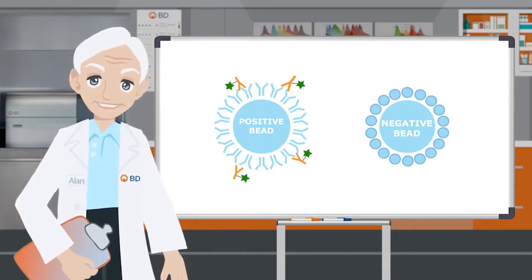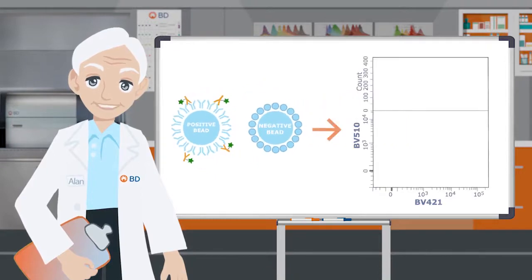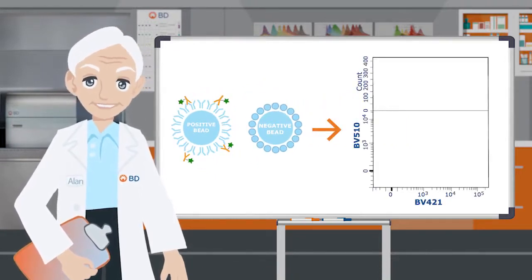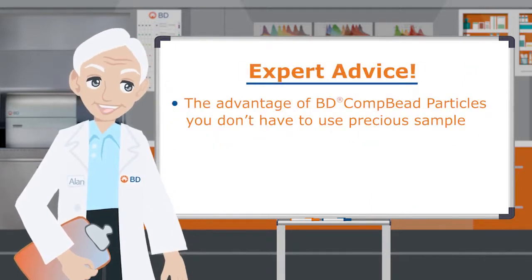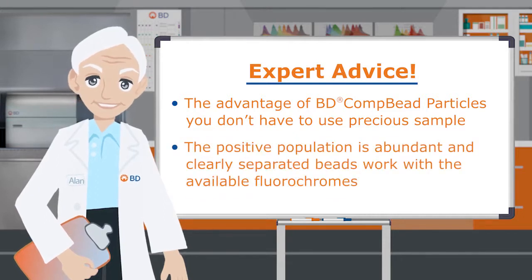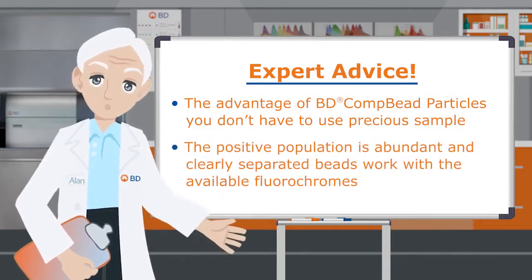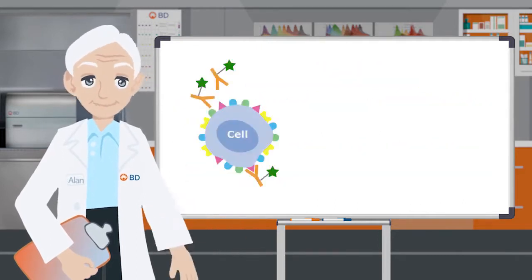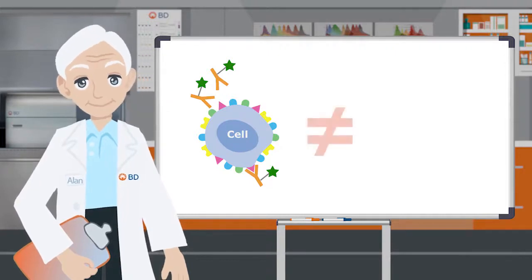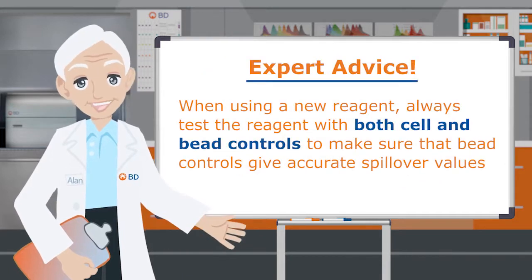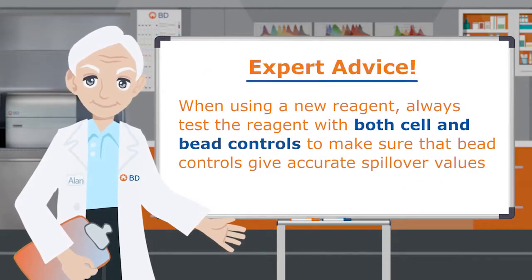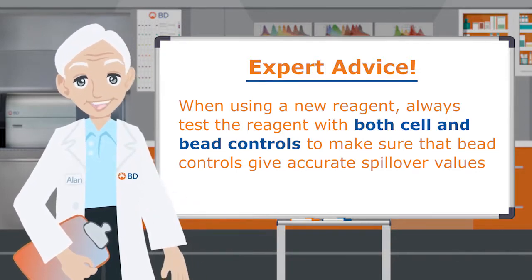When using cells is not practical, antibody capture beads can be used as a valid alternative for most fluorochromes. BDComp bead compensation particles, for example, are coated with anti-immunoglobulin that bind most fluorescent conjugated antibodies, acting as a surrogate for stained cells. The advantage of BDComp beads is that you don't have to use precious samples, and the positive population is abundant and clearly separated. The beads work with most of the available fluorochromes. However, it is important to note that for some fluorochromes, the spillover values on beads can be significantly different from similarly stained cells. So when using a new reagent, it's always best to first test the reagent with both cells and bead controls to make sure that the bead controls give accurate spillover values equivalent to cells.